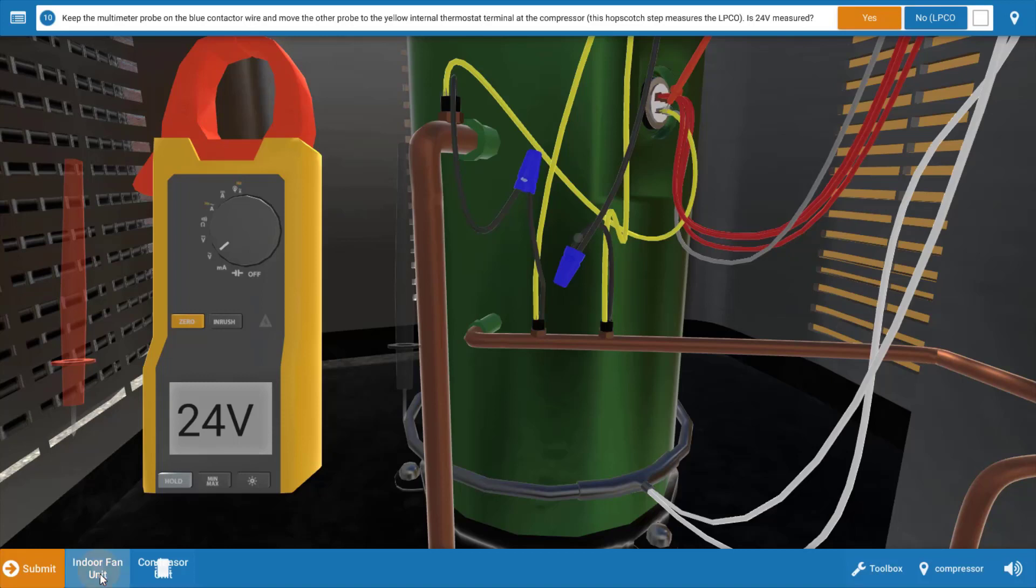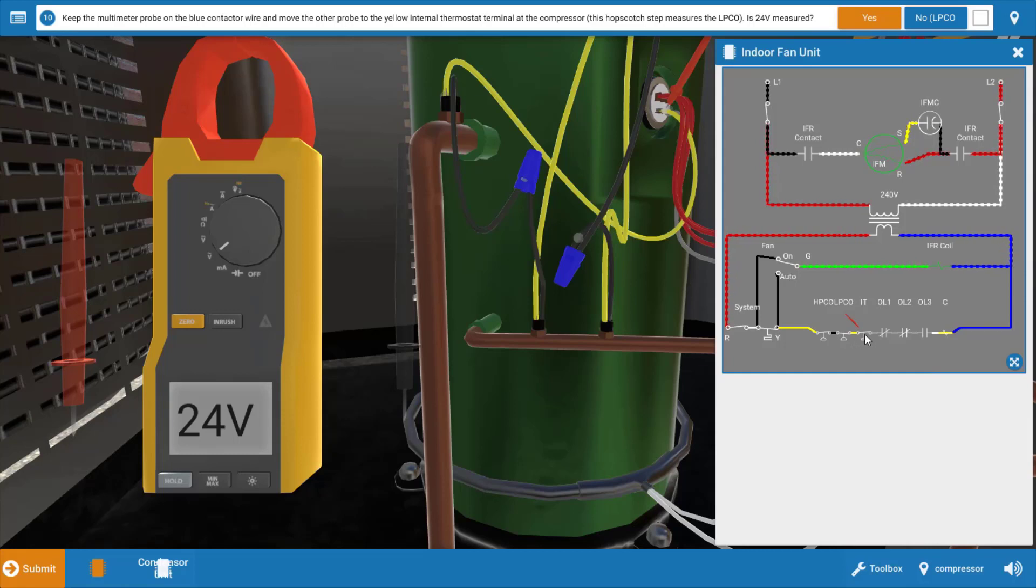So again, if you want to look at the wiring diagram, we can see our meter lead placement here coming out of the low and high pressure cutouts. We have voltage. So now we're down to the internal thermostat as well as the overloads.